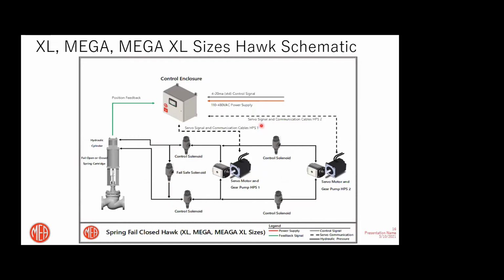Additionally, here is an additional hydraulic power source. So this is basically additional of these red boxes, I would say. These are actually used only to provide additional speed. So whenever you need more speed, you turn on both of the motors and pump more fluid from one side to the other, and the same way around. Whenever you need very precise positioning, and when it comes just to small movements, you operate only one. And whenever you need the full, very fast stroke, you utilize two.